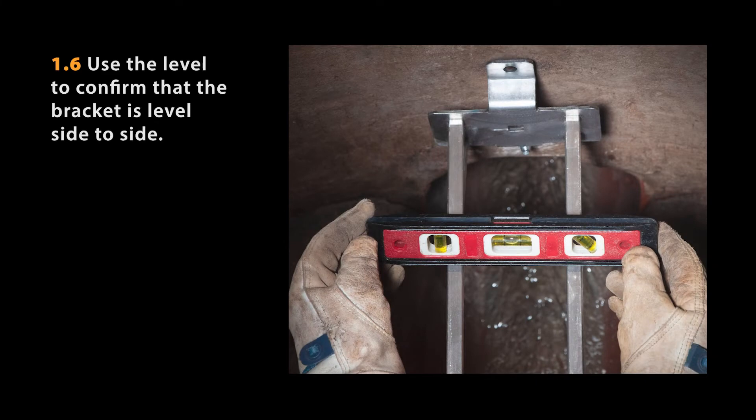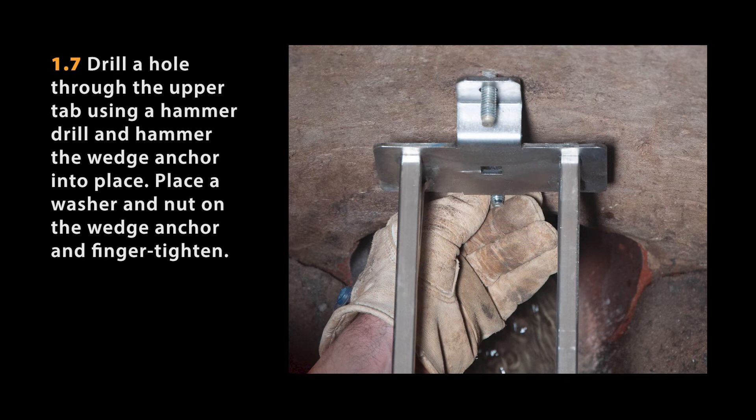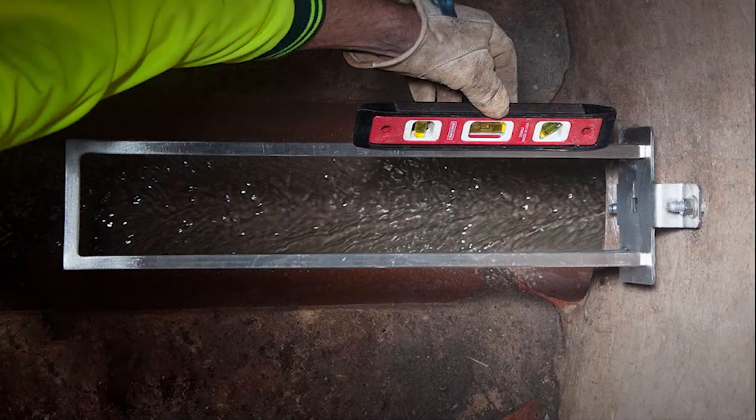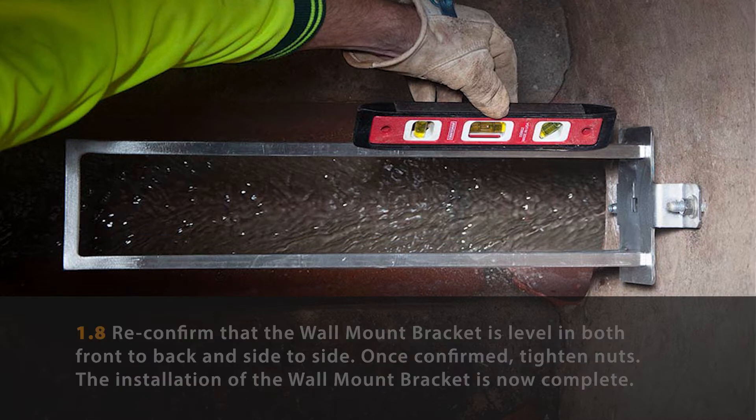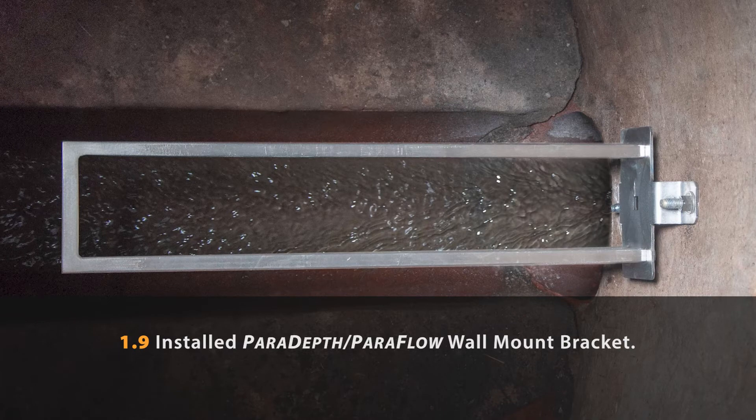Use the level to confirm that the bracket is level side to side. Drill a hole through the upper tab using the hammer drill and hammer wedge anchor into place. Place a washer and nut on the wedge anchor and finger tighten. Re-confirm that the wall mount bracket is level both side to side and front to back using the level. Once confirmed, tighten the nuts. The installation of the wall mount bracket is now complete.